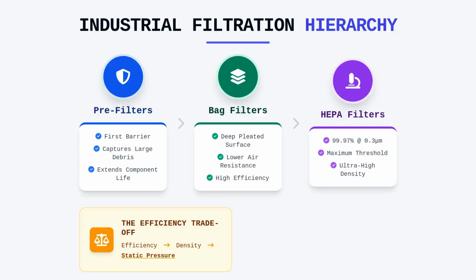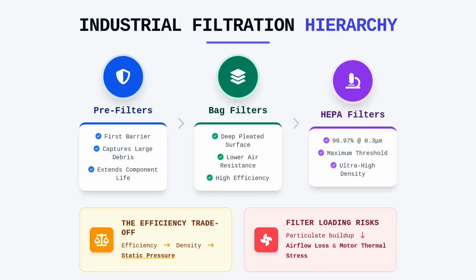However, as filtration efficiency increases, the physical density of the media also tends to rise, which directly impacts the static pressure across the system. We must monitor filter loading, as the accumulation of particulate matter increases air resistance, forcing the fan to work harder, which can lead to reduced airflow and potential thermal stress on motors.